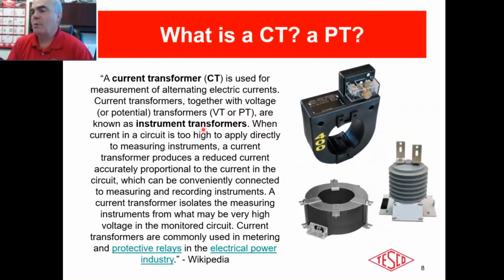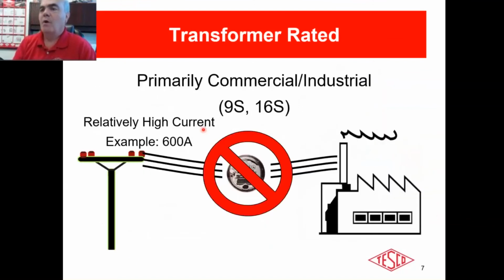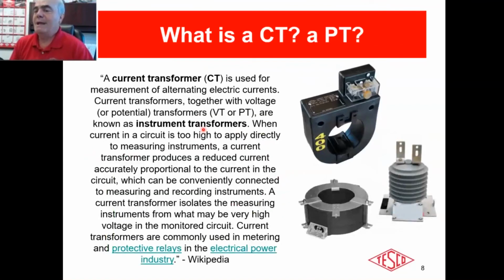An instrument transformer is a transformer that has a rated accuracy of at least 0.3% accuracy or better. When I say 0.3%, I mean that you're getting 99.7% of the anticipated ratio or better. All right, that's your definition of an instrument transformer. What we do with these instrument transformers, and similarly on a PT, we're stepping down the voltage. So what we're doing is we're taking those 600 amps and we're stepping it down to something that we can handle inside the meter. All right, which means that the meter is not in the direct service line.